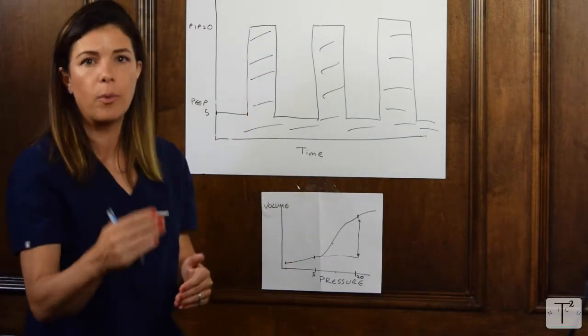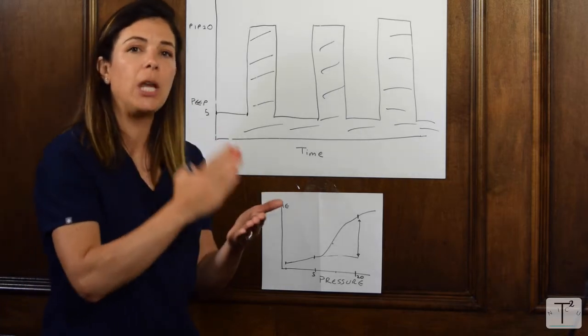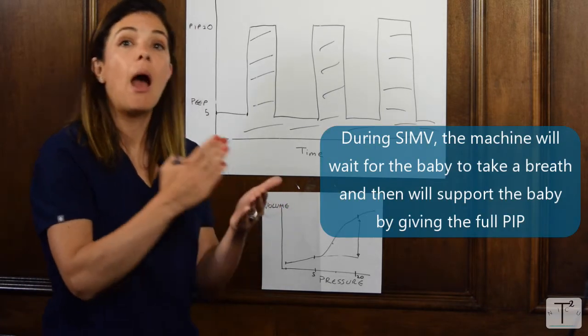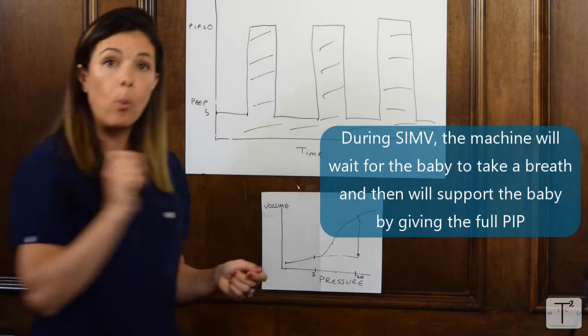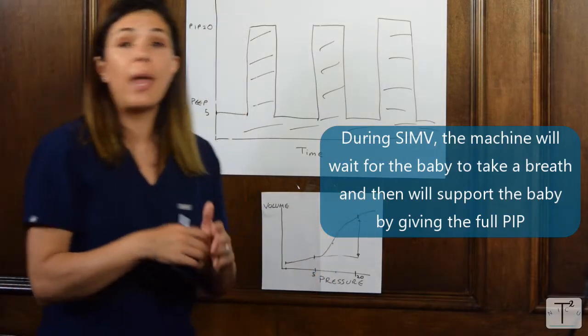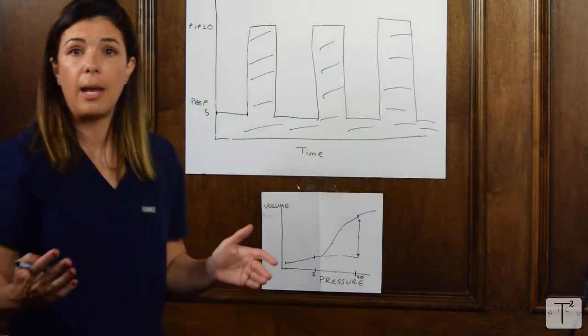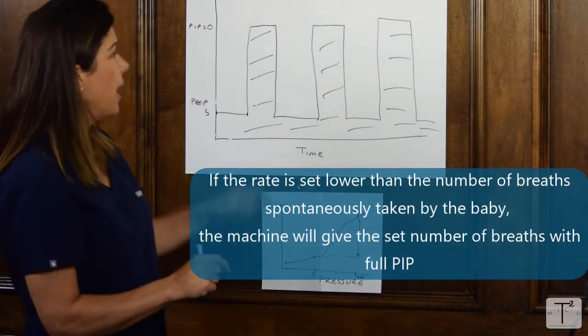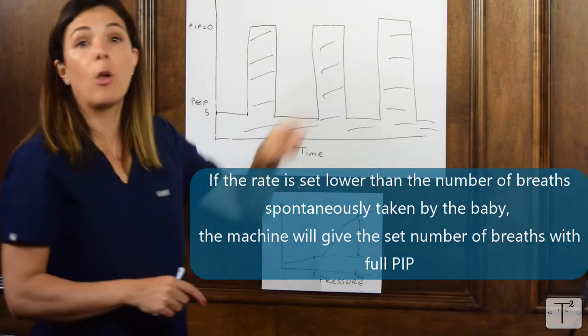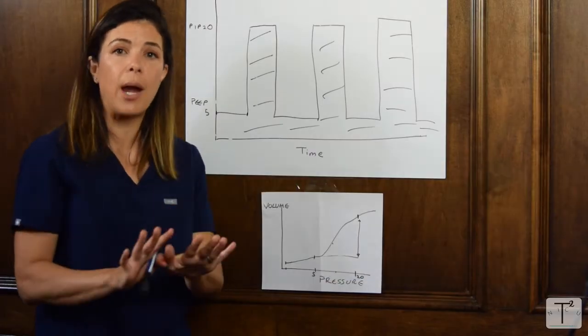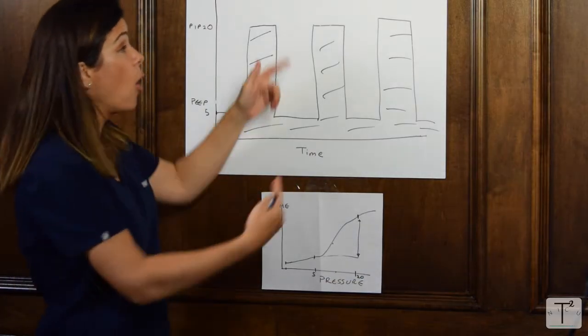Say you set the rate at 30, and the baby is breathing 40 times a minute. For 30 of those breaths, the machine is going to give the full PIP. So if you're breathing 40 times a minute, and the rate is 30, then there's 10 breaths, which the machine is not giving the PIP to.